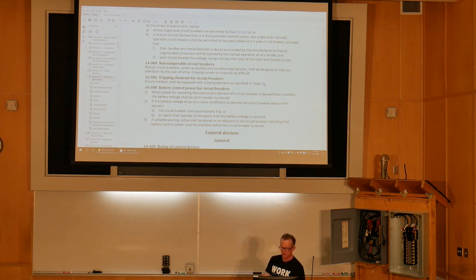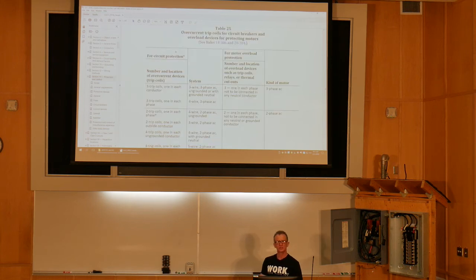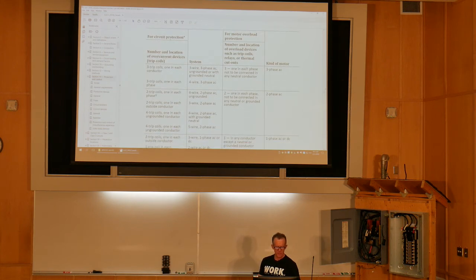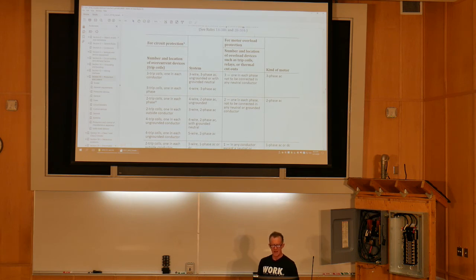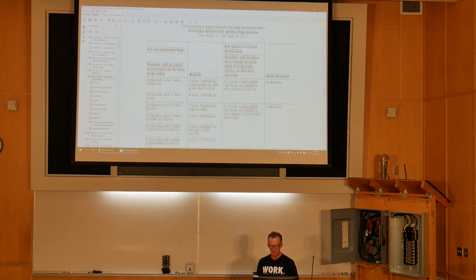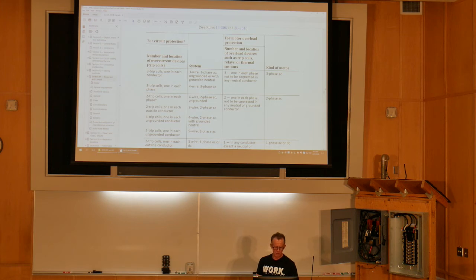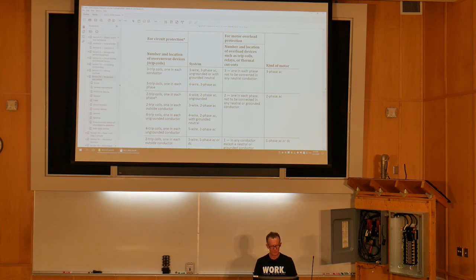Let's take a peek here at Table 25. So, circuit protection. This is the overcurrent part, and this is the overload part. This is also used in Section 28, with motors, when you use overloads. Here we're looking at circuit protection: number and location of overcurrent devices, the system, and then how many trip coils. So 3 trip coils, 1 in each conductor, 3-wire, 3-phase ungrounded system. For you 3rd and 4th year people, you need to understand this right here.